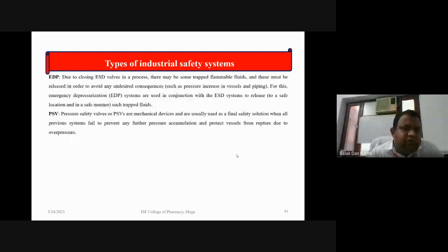Due to closing of the ESD valve in the process, there may be some trapped flammable fluids, and these must be released in order to avoid any undesired consequences such as pressure increase in vessels and piping. For this, emergency depressurization systems are used in conjunction with the ESD system to release the trapped fluids to a safe location in a safe manner. PSV, pressure safety valves, are mechanical devices that are usually used as a final safety solution when all previous systems fail, to prevent any further pressure accumulation and protect the vessel from rupture due to overpressure.